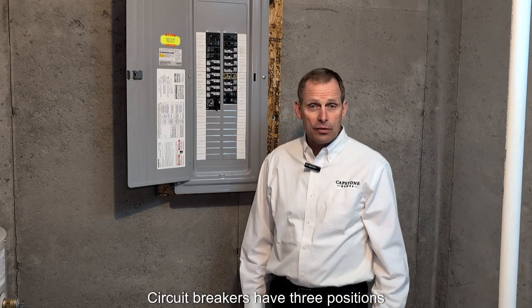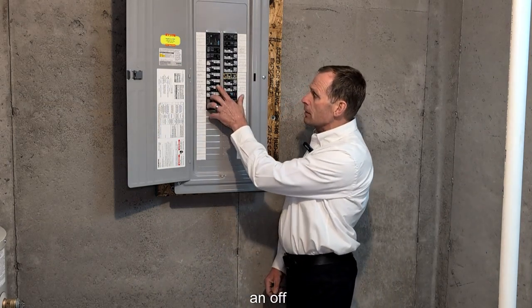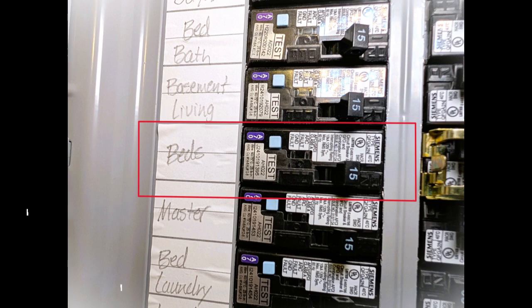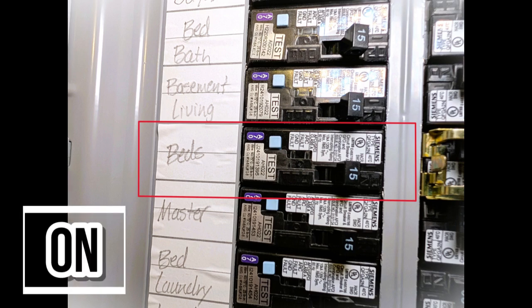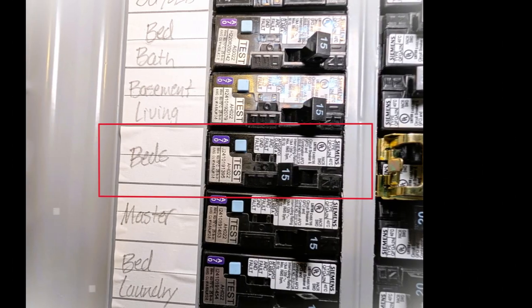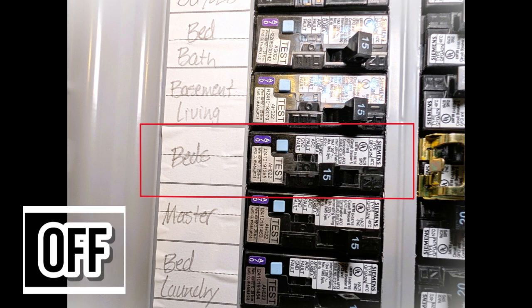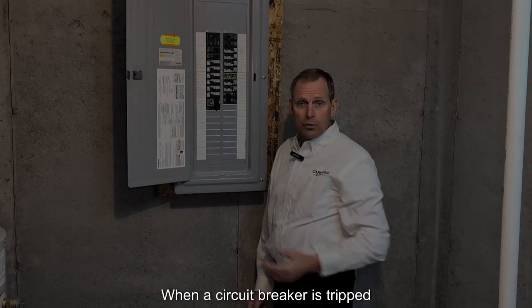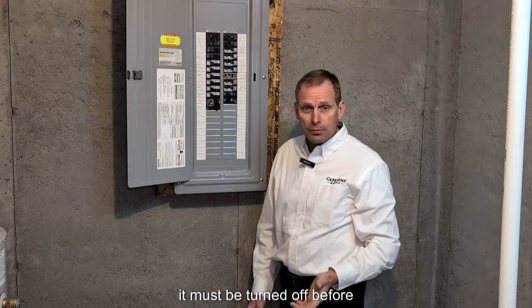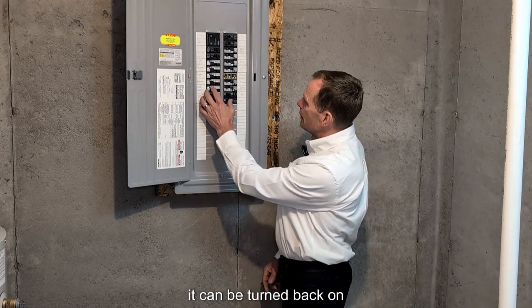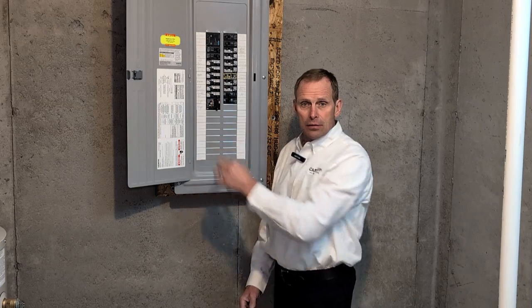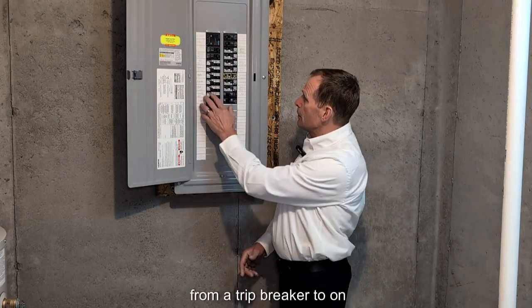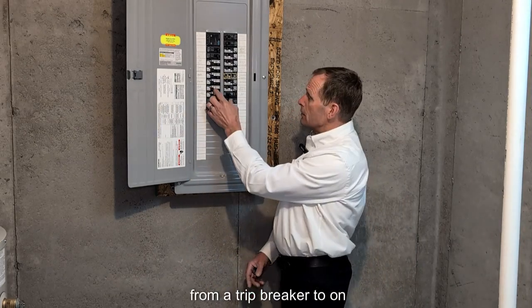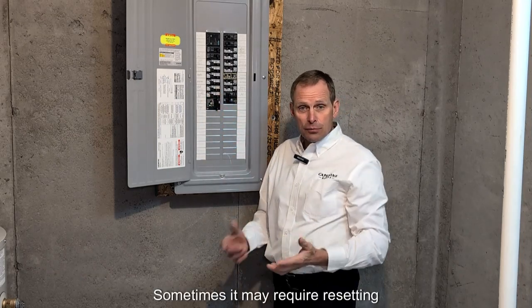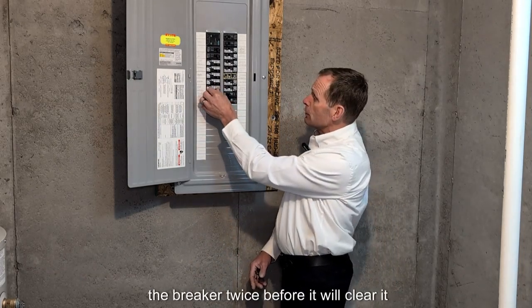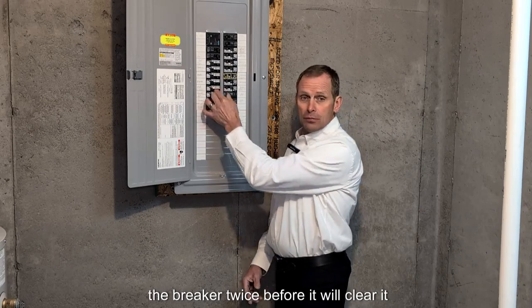Circuit breakers have three positions: an on, an off, and a trip position. When a circuit breaker is tripped, it must be turned off before it can be turned back on. Simply switching the breaker from trip to on will not reset it. Sometimes it may require resetting the breaker twice to clear it.